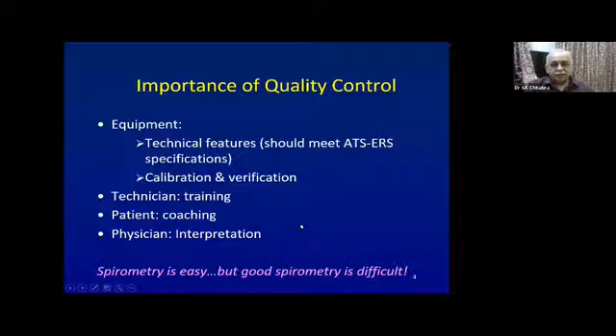Now there are two kinds of equipment. One are the flow measuring devices. These are called pneumotacs. Pneumo means air, tac means rate. Then there are volume measuring devices. Now flow measuring devices measure flow, and from the flow by integration, that is electronic integration, we measure the volume. In volume measuring devices, we measure volume and we differentiate the signal to get flow. So actually we are recording one signal directly and getting the other by derivation.